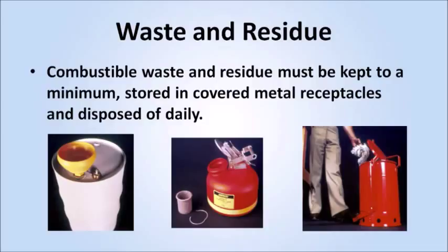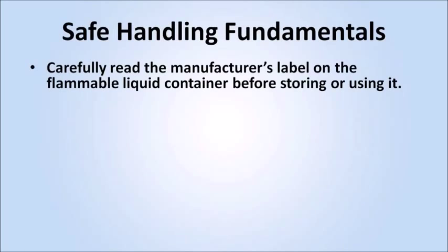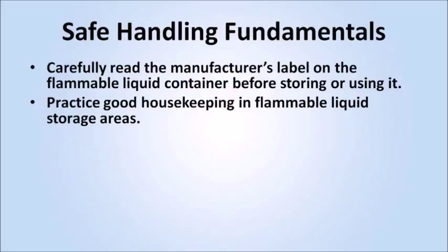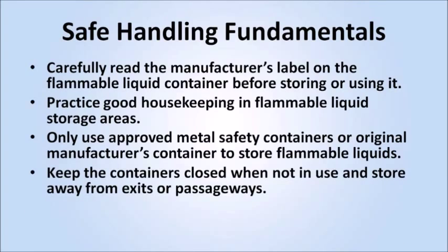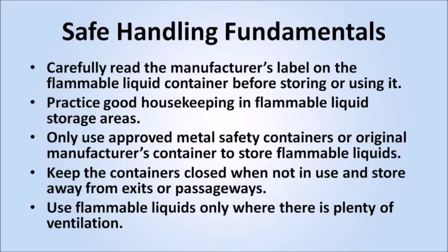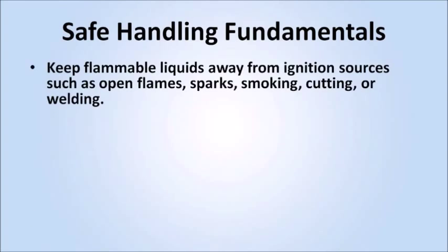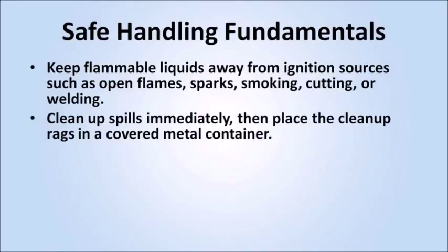Combustible waste and residue must be kept to a minimum, stored in covered metal receptacles, and disposed of daily. Here are some safe handling fundamentals: carefully read the manufacturer's label on the flammable liquid container before storing or using it. Practice good housekeeping in flammable liquid storage areas. Only use approved metal safety containers or the original manufacturer's container to store flammable liquids. Keep containers closed when not in use and store away from exits or passageways. Use flammable liquids only where there is plenty of ventilation. Keep flammable liquids away from ignition sources such as open flames, sparks, smoking, cutting, or welding. Clean up spills immediately, then place the cleanup rags in a covered metal container.